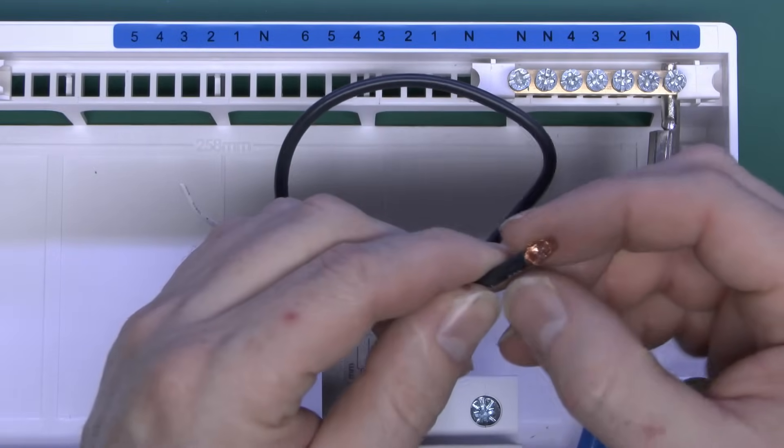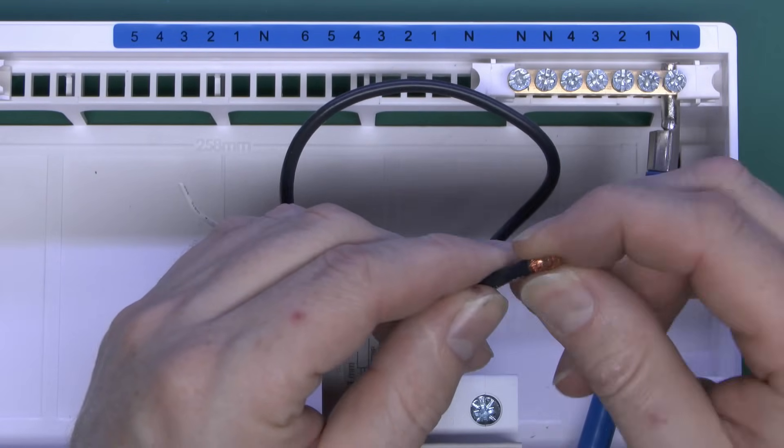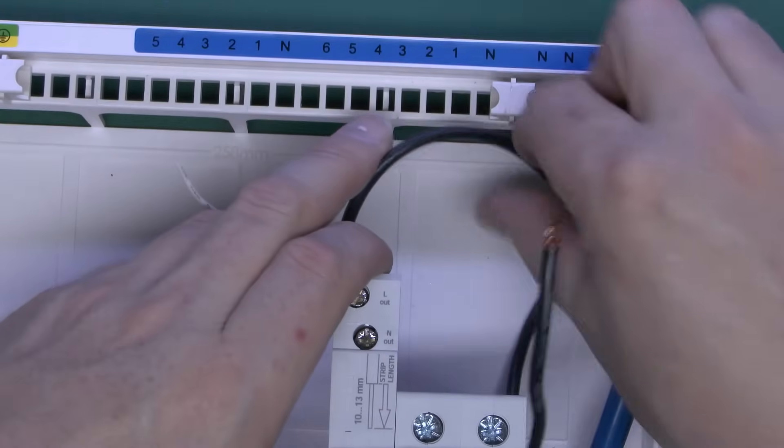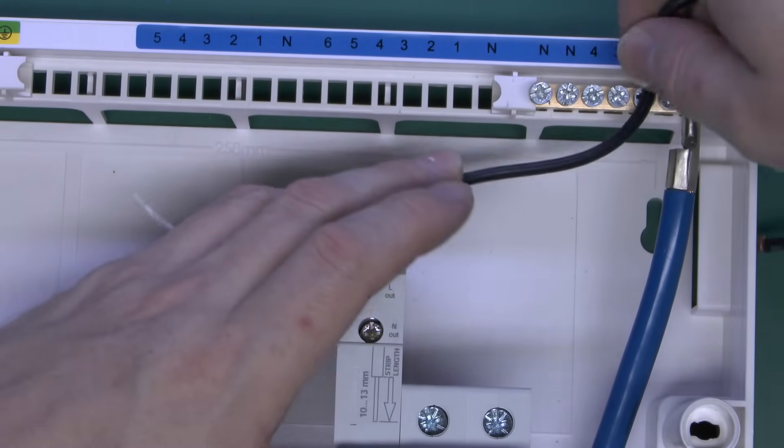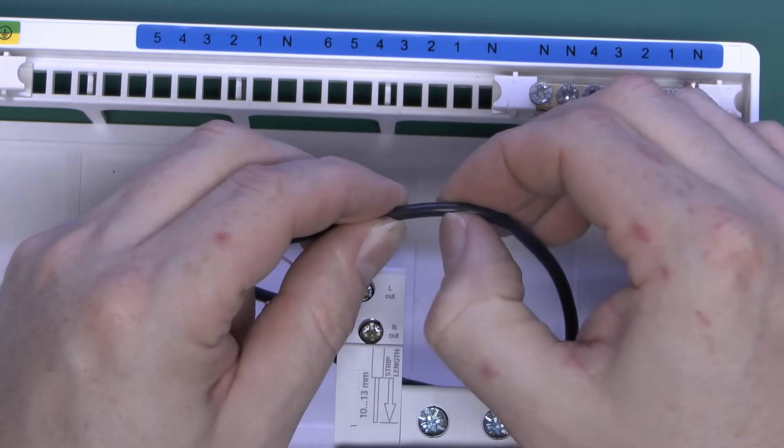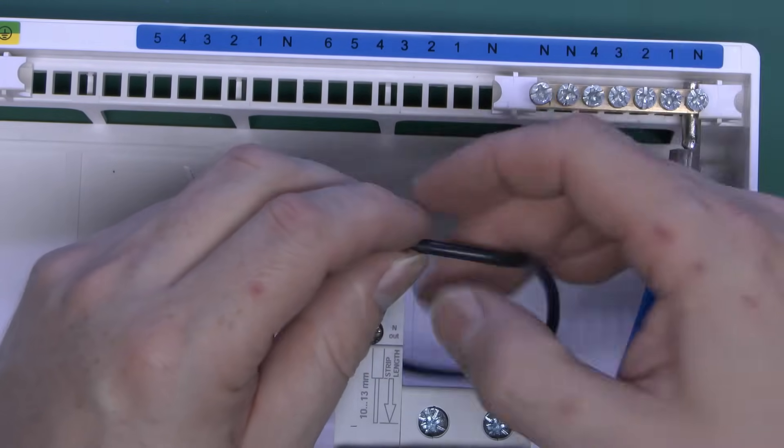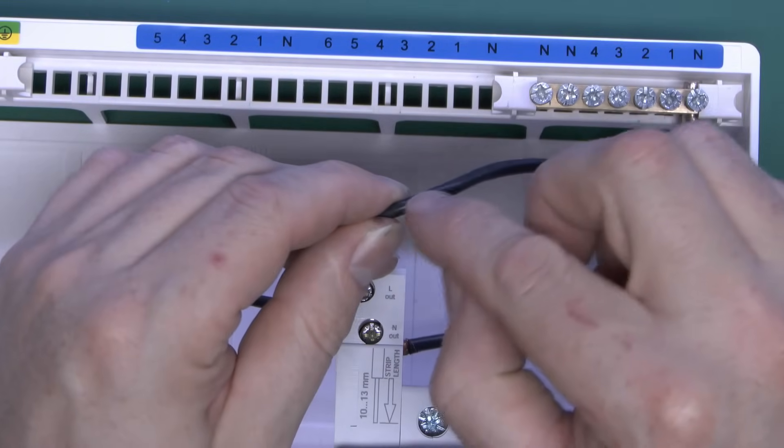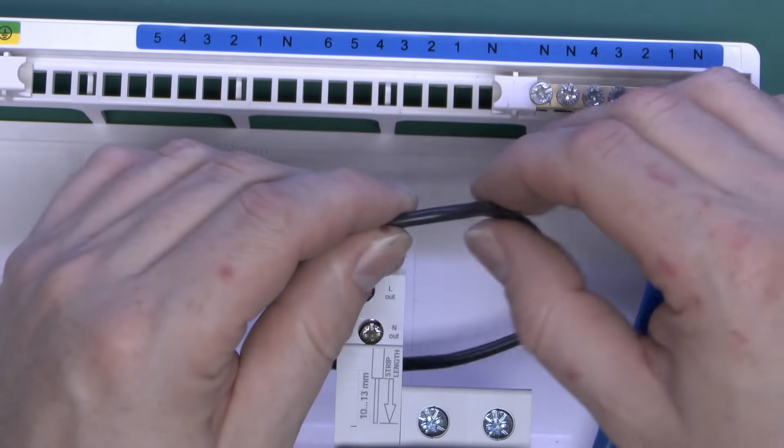So let's say this one is actually some kind of welded arrangement or others have say pins on like that so although it may be tempting to cut the wires off and just make them sort of nice and neat and tidy then it can result in problems with that very fine stranded wire going into the screwed connection and if you do cut it off of course you can always just crimp on a pin on the end there which of course avoids the problem.